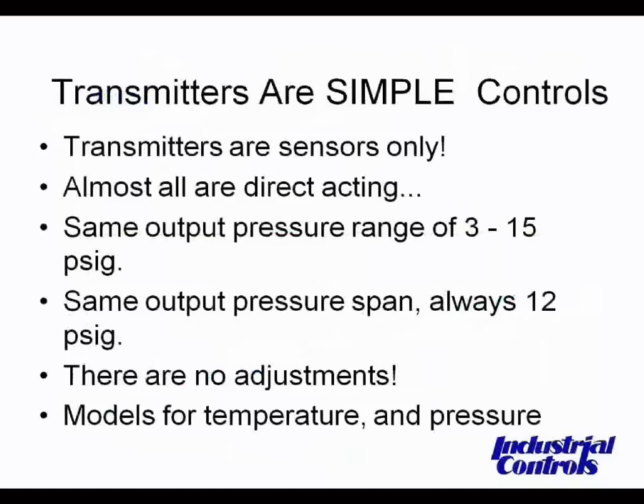The transmitters can be fed main air either from the receiver controller or it can be done remotely. When in the field or troubleshooting, you want to know where that restrictor is. Generally, start at the controller and see if that restrictor is feeding the transmitter, or if the restrictor is blocked within the receiver controller.